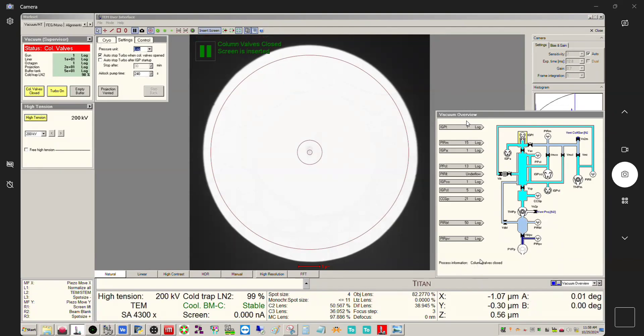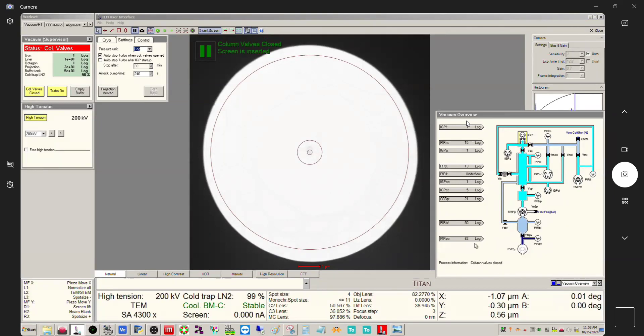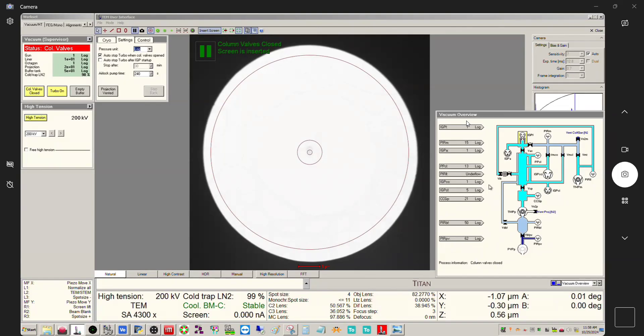Log is a little bit, you know, they use this log because you can have a wide range of levels in vacuum, many orders of magnitude. So that's why they have the log units. Basically, every time there's a 10% change, you're going to see a change in the log unit. So if you go from, say, a 10% increase, that would be five to six. If it's a 10% decrease, it'd be five to four. I know this is how it works on the Themis and the Talos, these newer ones. I'm not exactly sure if it's quite that with the Tecnai. I think it still is with the older Tecnais and the older Titans, but I'm not entirely sure. But I prefer to leave it in Torr because Torr is Torr, regardless of whether you're on a new microscope or an old microscope.